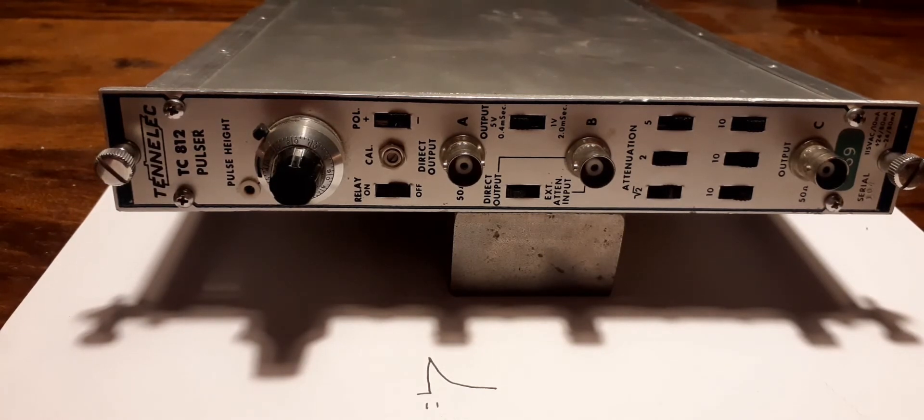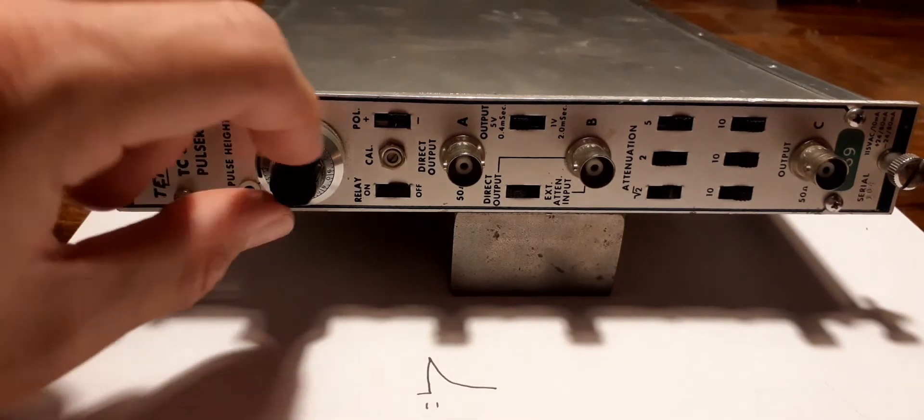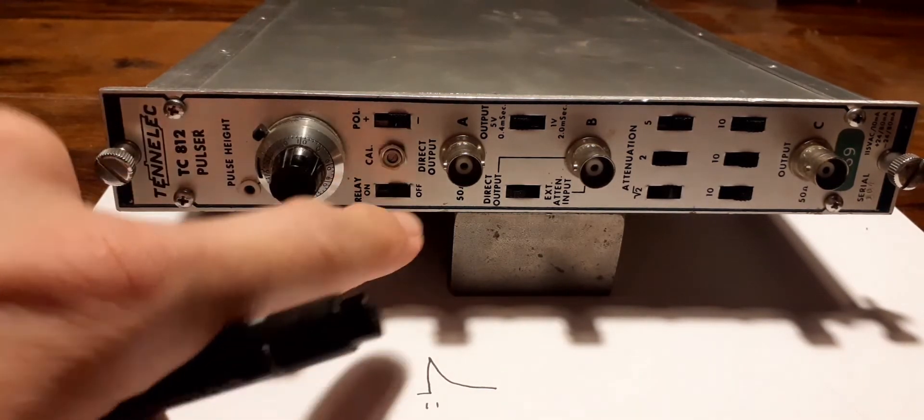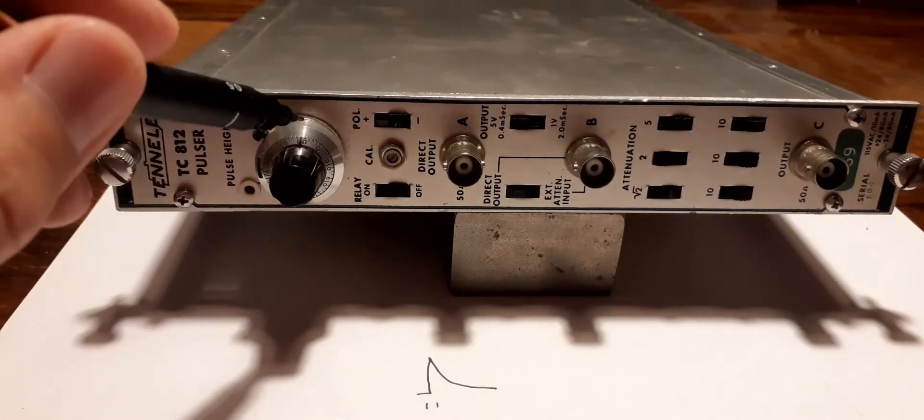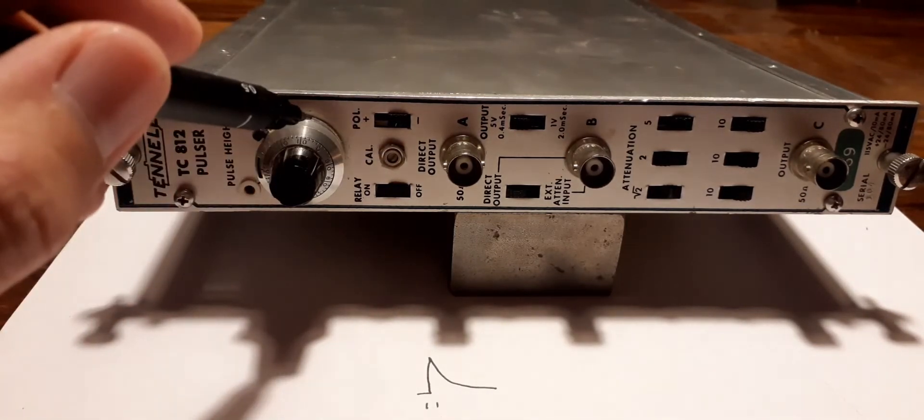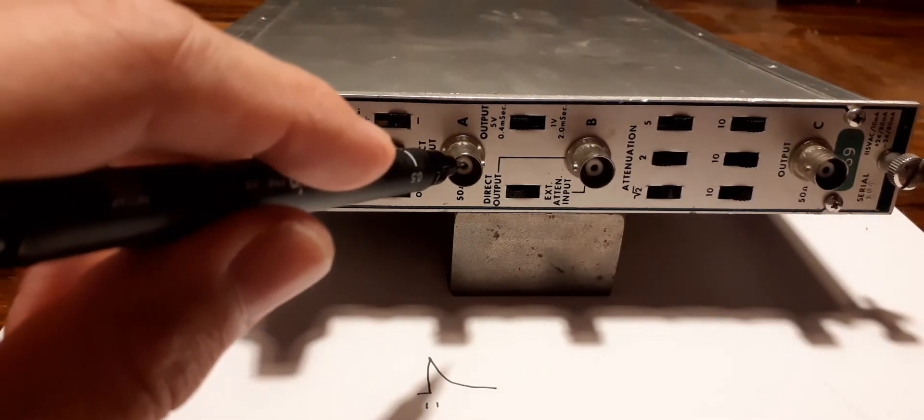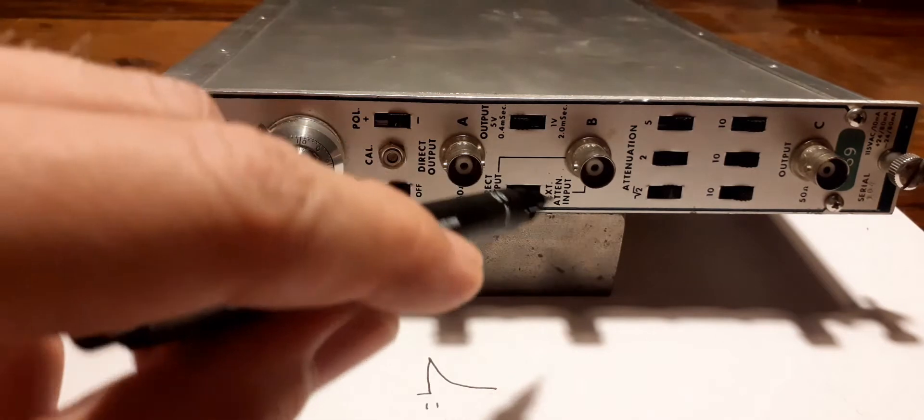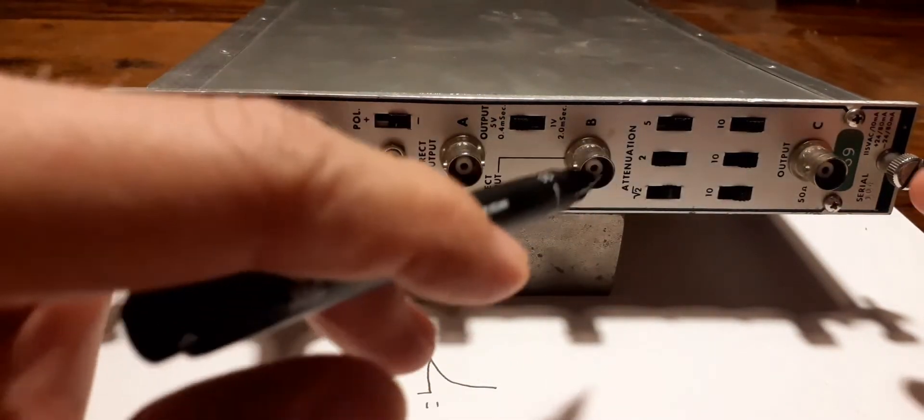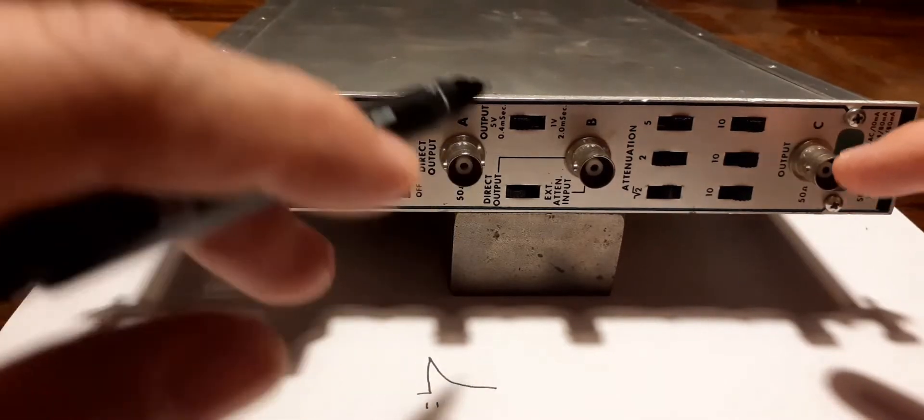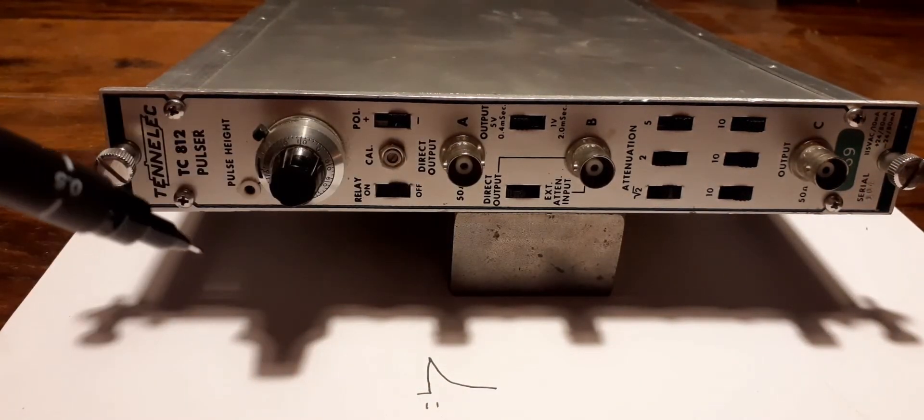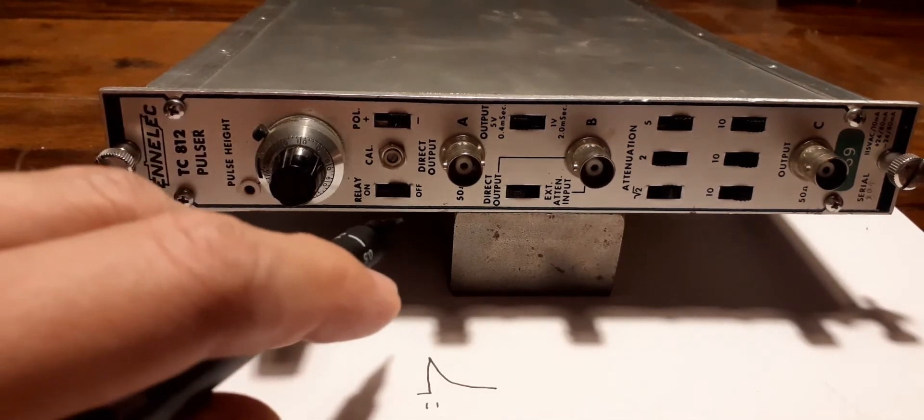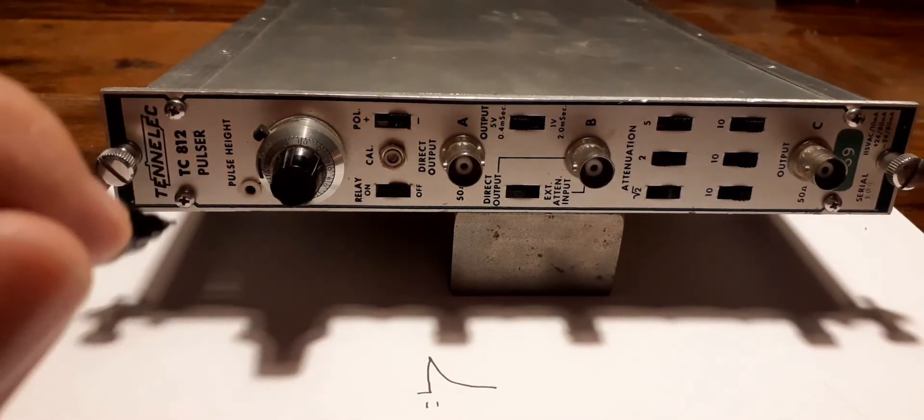What we have here is a 10-turn pot with a Vernier knob, a relay on/off, a calibration that's just a resistor in series with the pot, a polarity switch, and an output. The other things here are this attenuator section which can be used as a separate attenuator or as an attenuated output. You can change the polarity, the pulse height, and turn the pulser on and off—that's a very important feature.